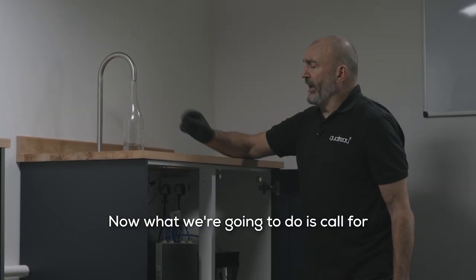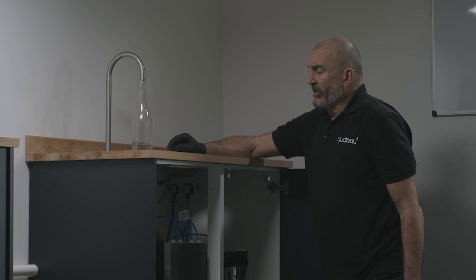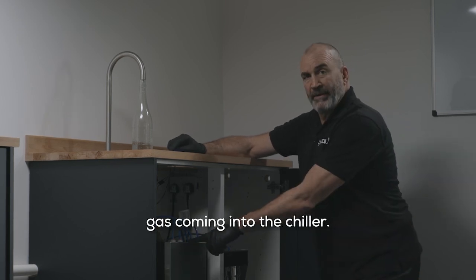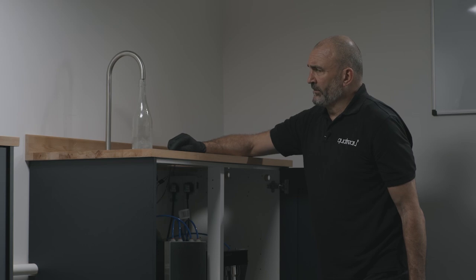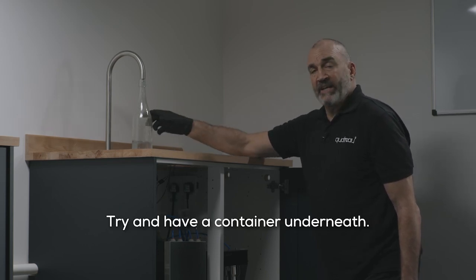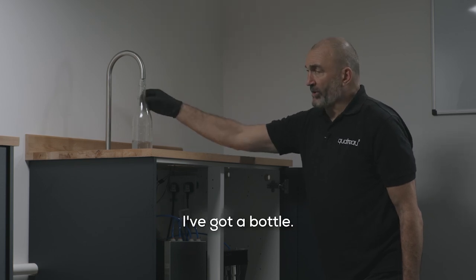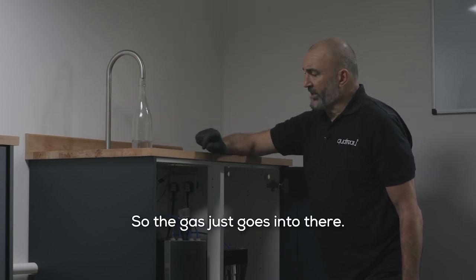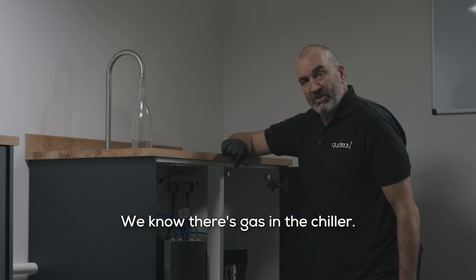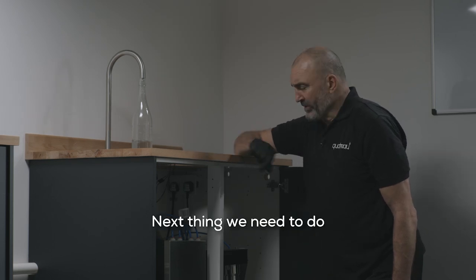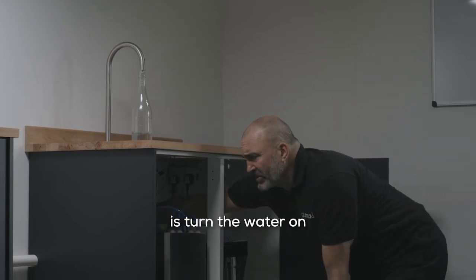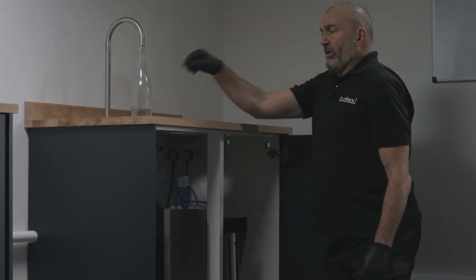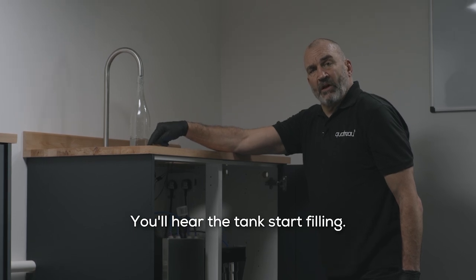Now what we're going to do is call for the sparkling function on the drip tray, just so we know that there is gas coming into the chiller. You'll hear a burst of gas. Try and have a container underneath. I've got a bottle, so the gas just goes into there. So we know there's gas in the chiller. Next thing we need to do is turn the water on to the system. You'll hear the tank start filling.